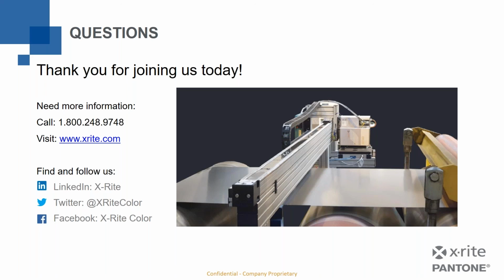So obviously that does lead to some wear and tear on the lamp, right? These devices are extremely precise in the fact that they're measuring every nanometer, which allows us to do really good compensation through calibration and so forth for the lamp as the lamp wears over time. And it's also why the vast majority of people who are using these have service contracts and things in place where we're using that to properly maintain the device.